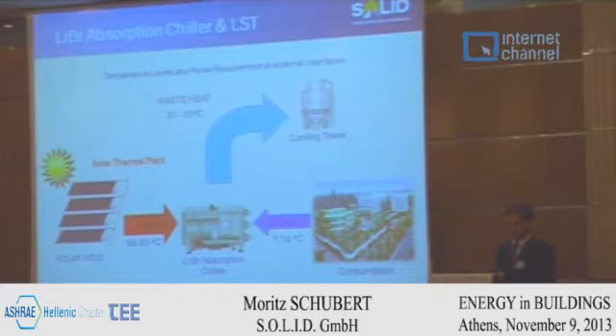This lithium bromide absorption chiller is normally driven at temperatures between 83 and 88 degrees, but you can also go lower than this. You can go down to 70, 75 degrees, or if you want to run it more efficiently, you can also go to 95 degrees. But then, of course, the solar thermal collector field runs less effectively at higher temperatures, so you always have to find a compromise between these.